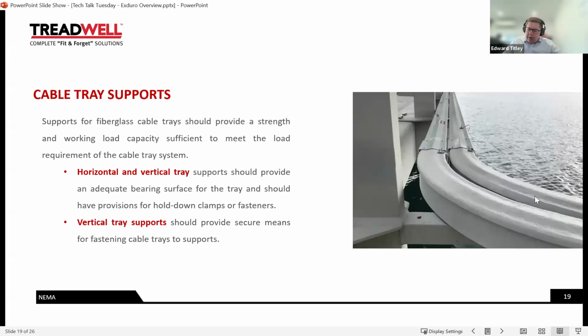Just on supports and on the way through, this is a cable trough. So this is a deeper, it's like a cable tray, but just deeper. And this is on a jetty to provide secure containment for cables and protection. Horizontal, but on supports, horizontal and vertical tray should provide adequate bearing surface and have provisions for hold down clamps or fasteners. So we offer a complete hold down clamp system in FRP with stainless channel nut, and vertical should provide secure means for fastening trays to support. So more on, happy to discuss on a project specific basis what that looks like. I'm not NEMA, so I can't tell you what they meant. By standard, we can certainly share advice and successes, what's worked well in the past, that sort of stuff.